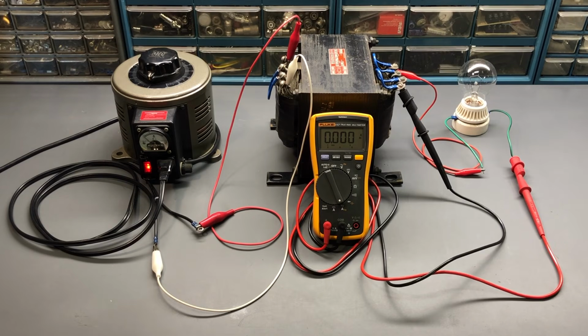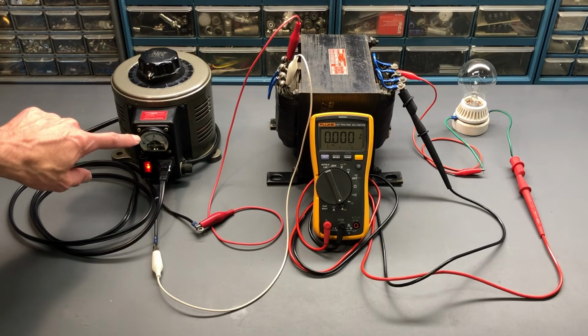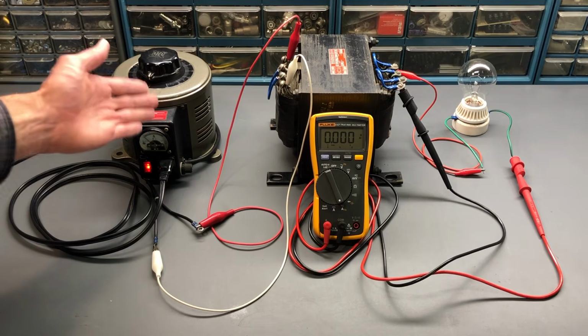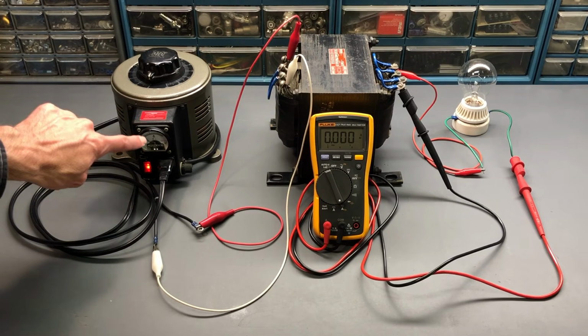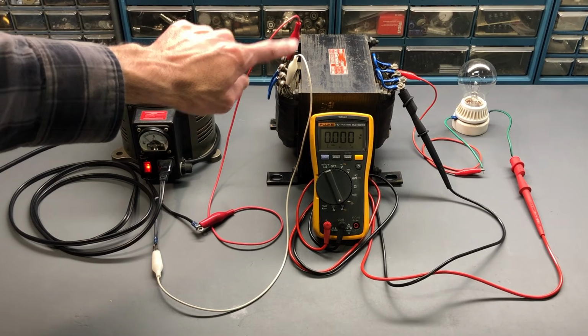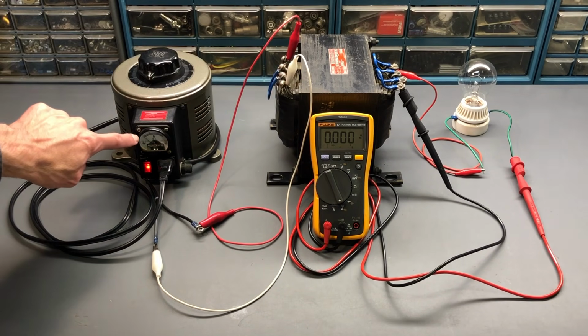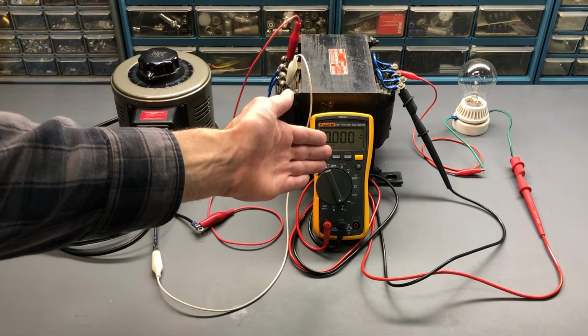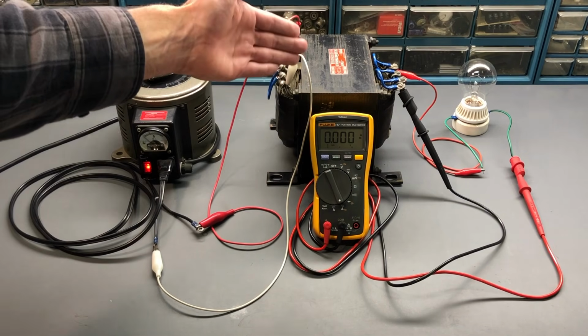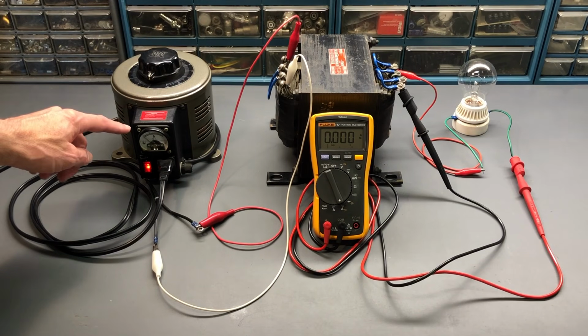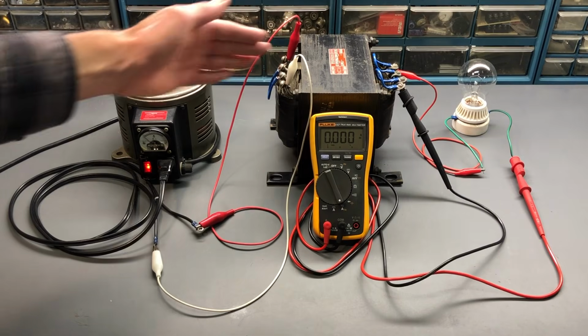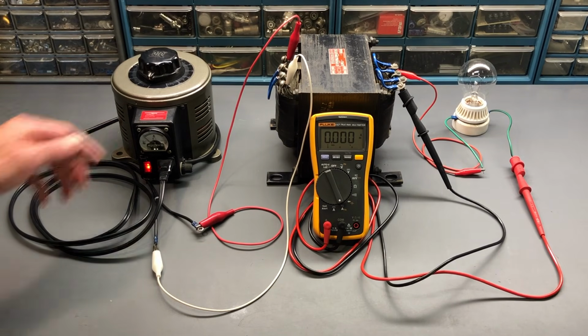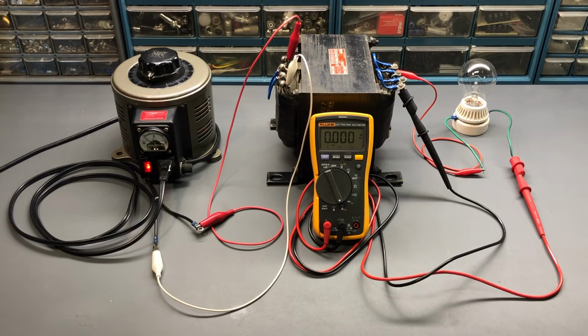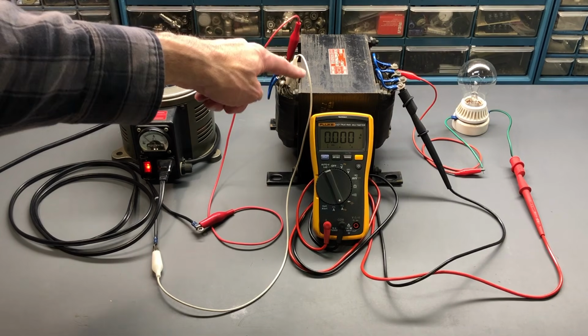It does work well, but there is one slight disadvantage to this setup, and that is if you have a Variac that has built-in metering, this meter is showing the total current flow of everything in the circuit, and it's going to show the current flow that is lost as heat in the transformer. So any indication on here is going to be the current flowing through the device you're testing, but in addition any current that's lost as heat in the transformer. That's typically not a lot. It is a small amount, but if you have a very sensitive amp meter in your Variac, the General Radio Variac that I previously showed in my setup is quite sensitive in the 1 amp setting, and it would show the current flow going through the transformer that's just being lost.